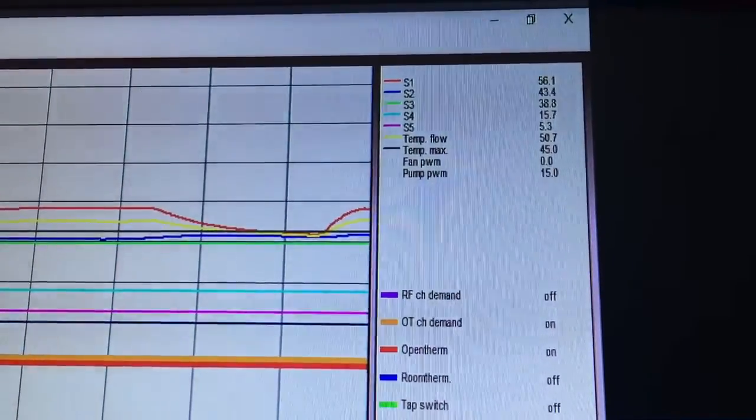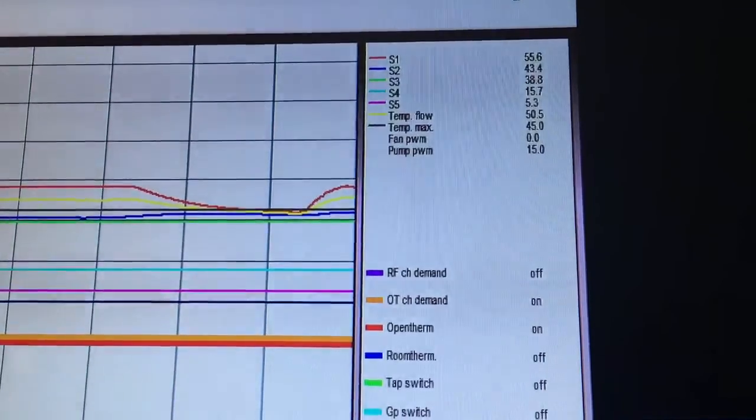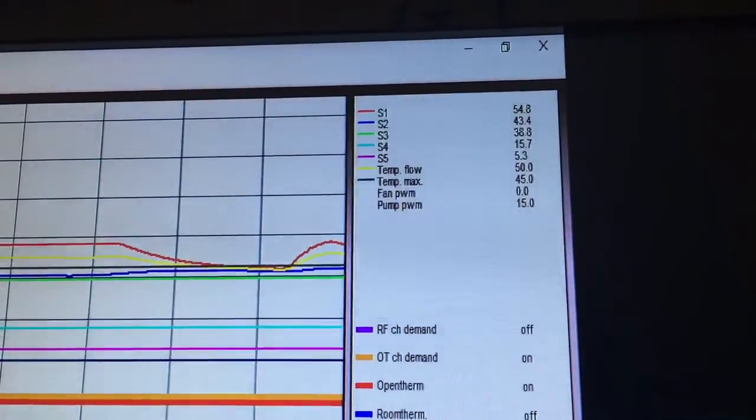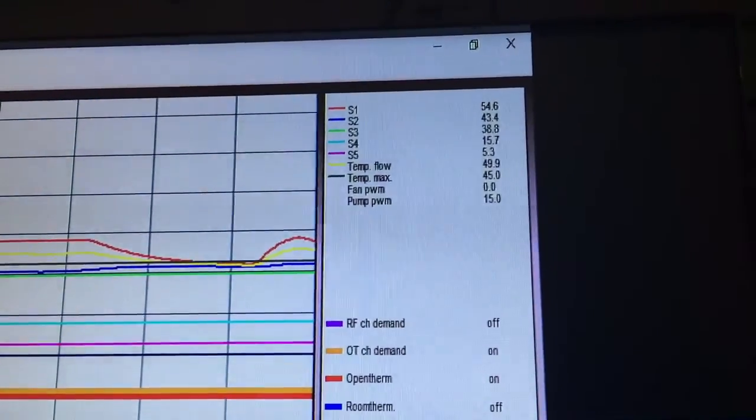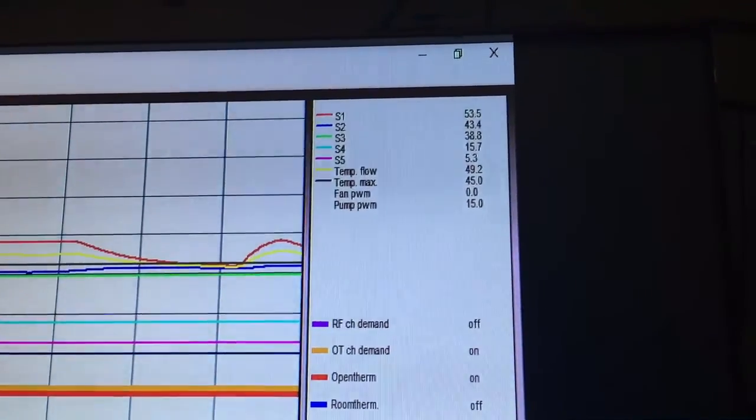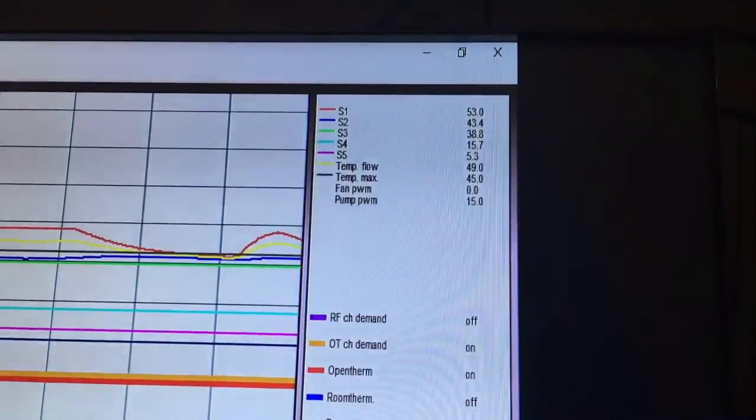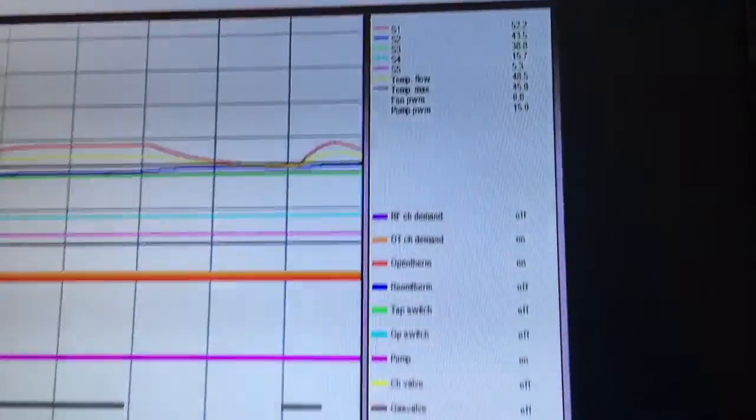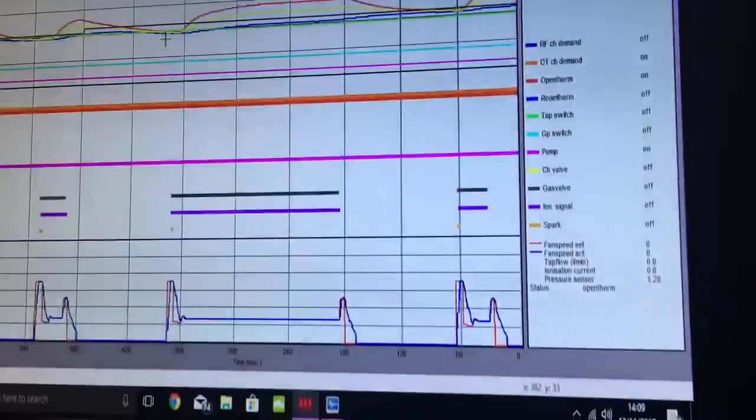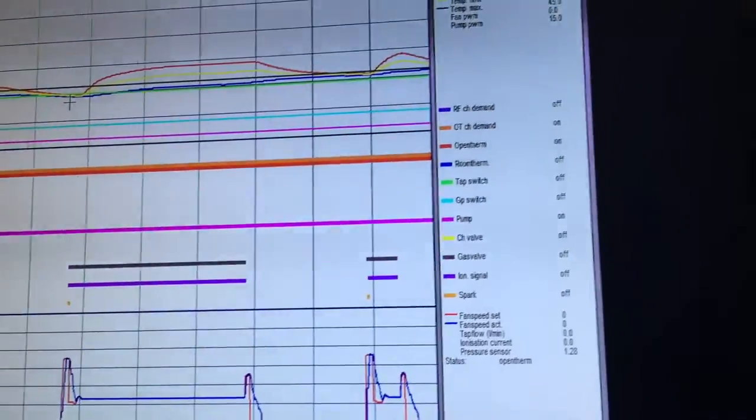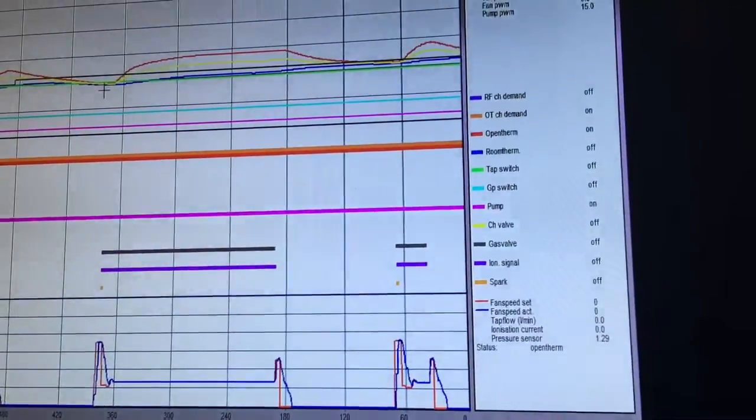But basically with a set point of 20 degrees, which is what it's based on, and curve 16, which I've set, it's giving us a required temp max of 45 degrees Celsius based on an outside air temperature 5.3 degrees. And what you can see is the boiler is cutting in and out on the gas valve because the heat emitter that I'm using is undersized to the appliance, so we are getting a little bit of cycling on the burner.